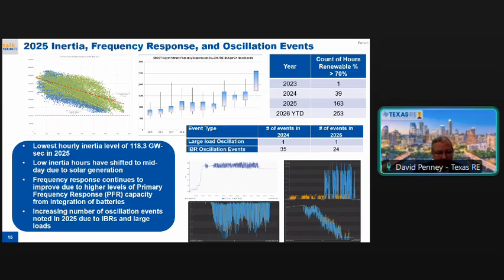The oscillation event on the top left-hand side is actually a large load that, when it ramped up to just over 300 megawatts, had control problems within that site causing the megawatts to oscillate, and they had to be asked to back down. The chart right below that is a battery that started oscillating its megavar output and caused some localized voltage issues in the 345 system it was connected to.